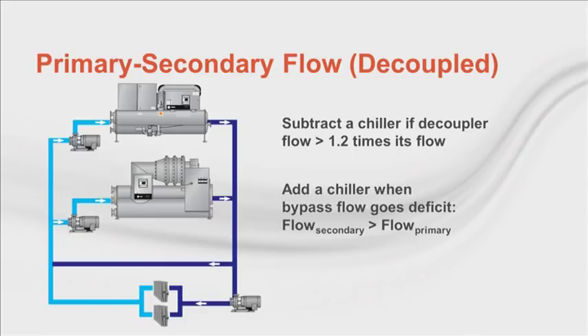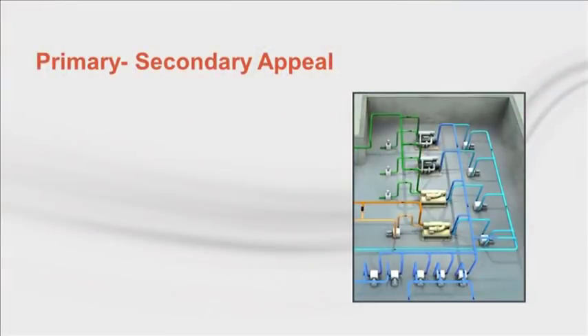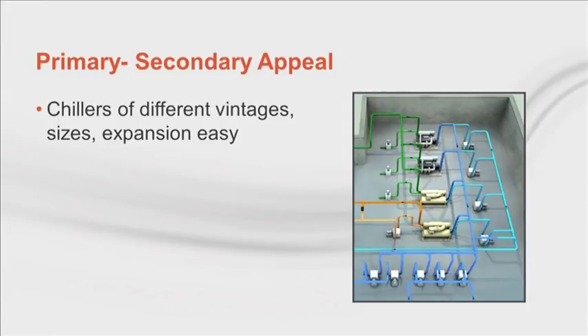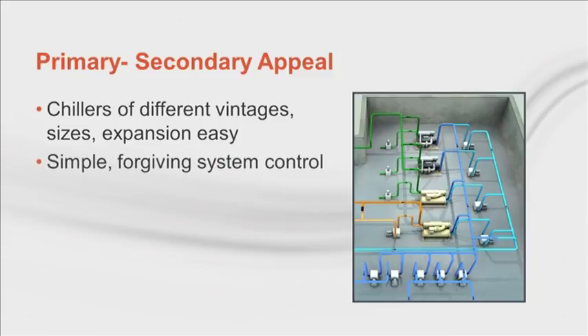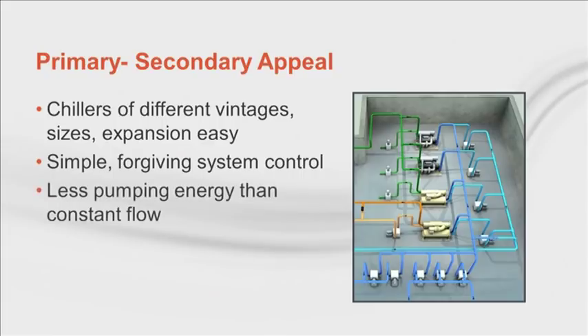Here I'm showing a dedicated primary pump per chiller and different styles of chillers. The dedicated pump arrangement is typical and allows for the pump to be commissioned for the flow that is expected through its chiller. The primary pump is constant speed, while the building pump or secondary pump is variable speed. The appeal of this configuration is how it accommodates chillers of varying ages, flow rates, pressure drops, and capabilities. For this reason, it is relatively easy to expand the system. The system controls are forgiving and straightforward. Pump energy is reduced because the secondary pump energy falls with the cube of the load reduction.